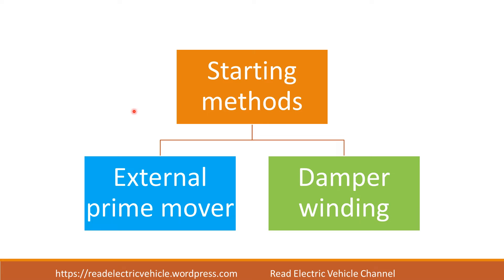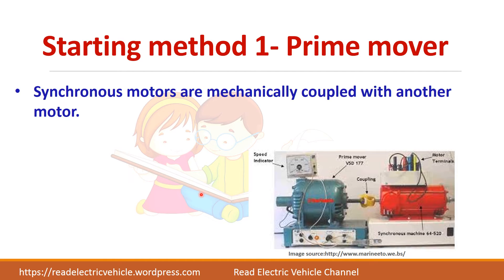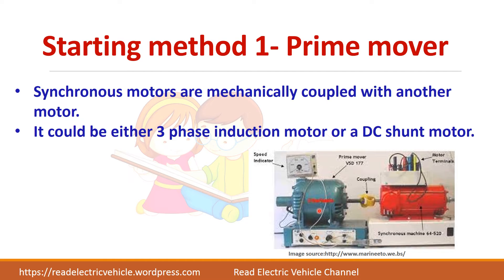There are different starting methods. One is using an external prime mover and another one is using damper winding. When using a prime mover — which is what we normally see in the lab — another machine is coupled to it and using that we start the synchronous machine. It could be either a three-phase induction motor or a DC shunt motor.